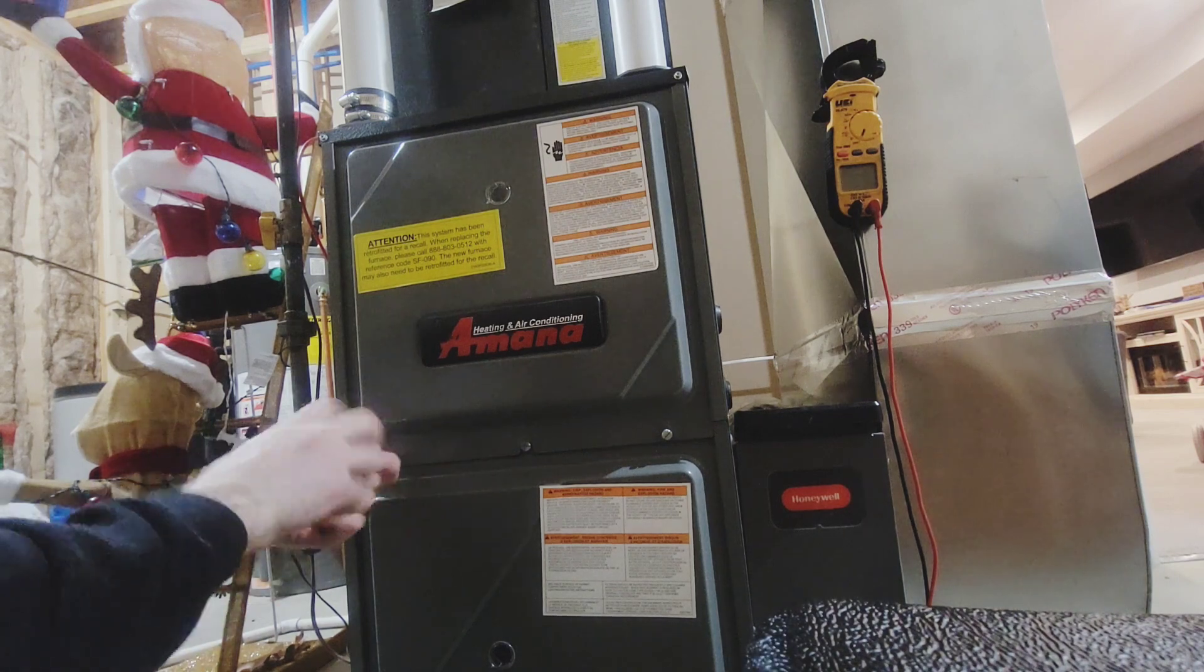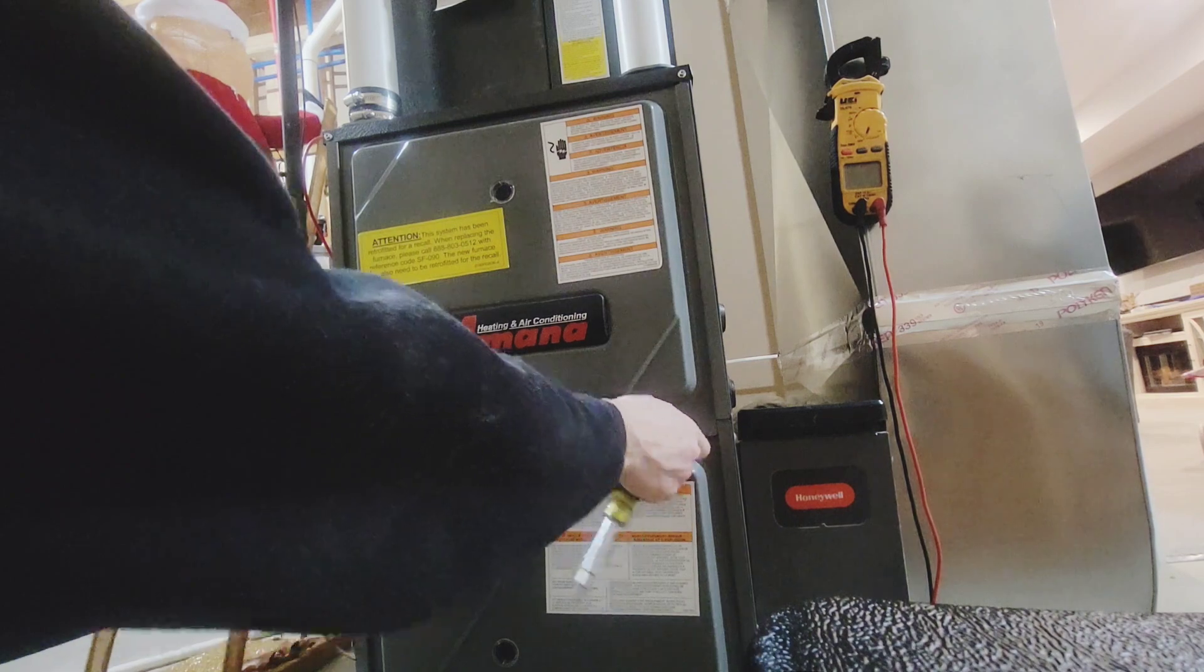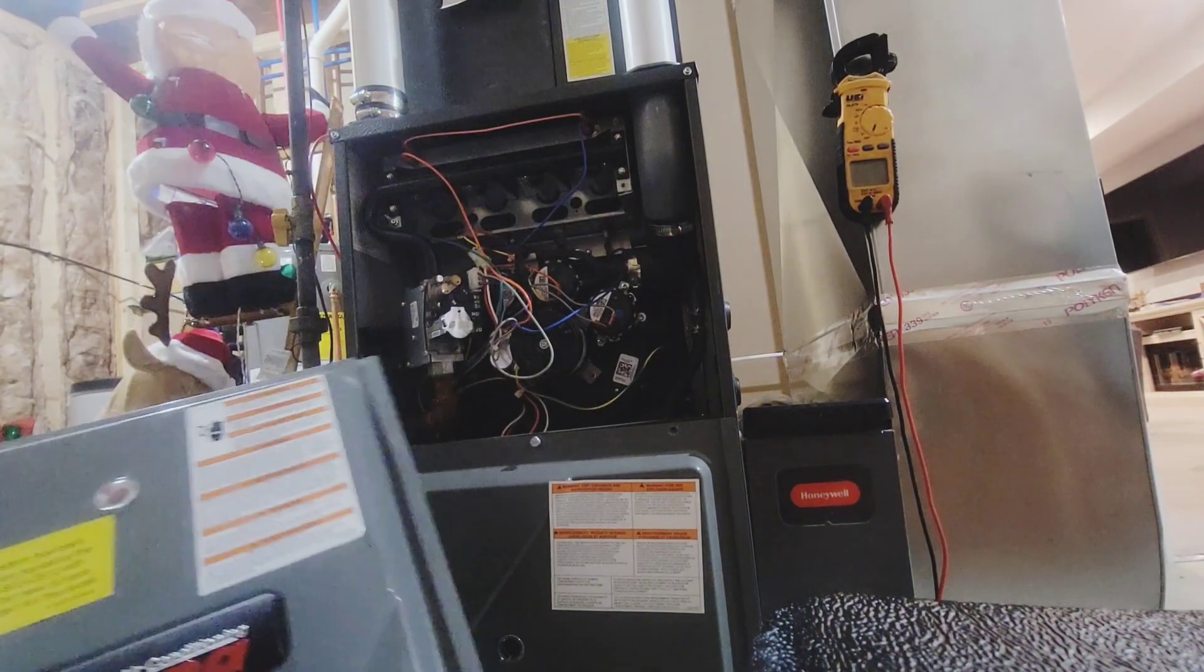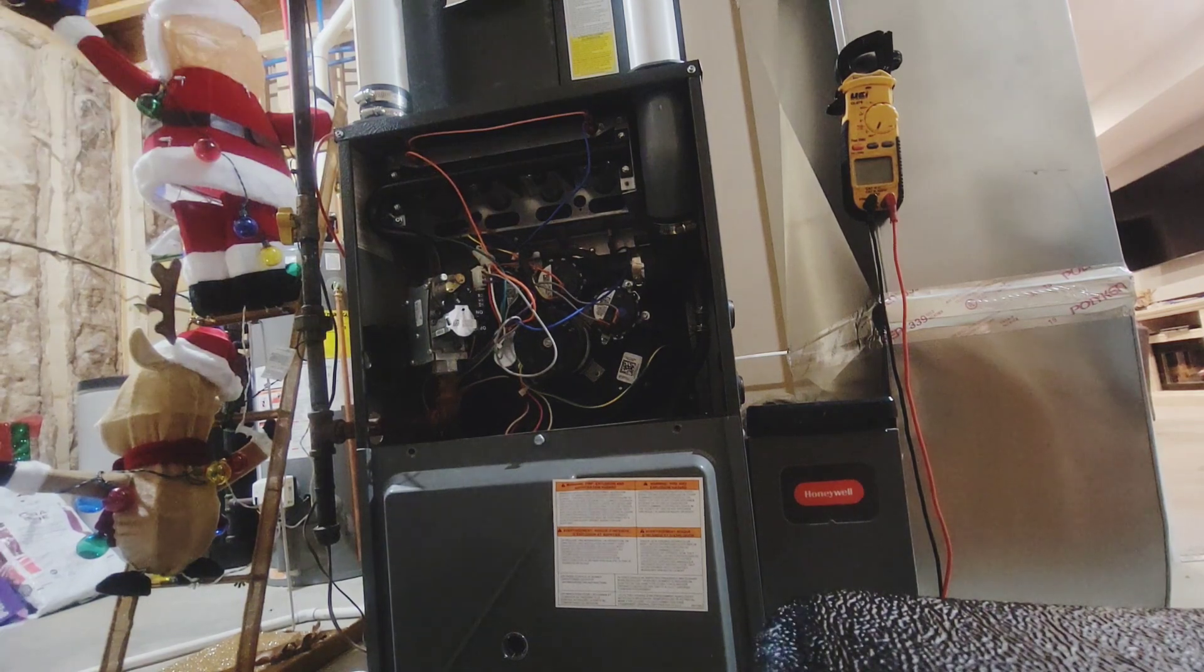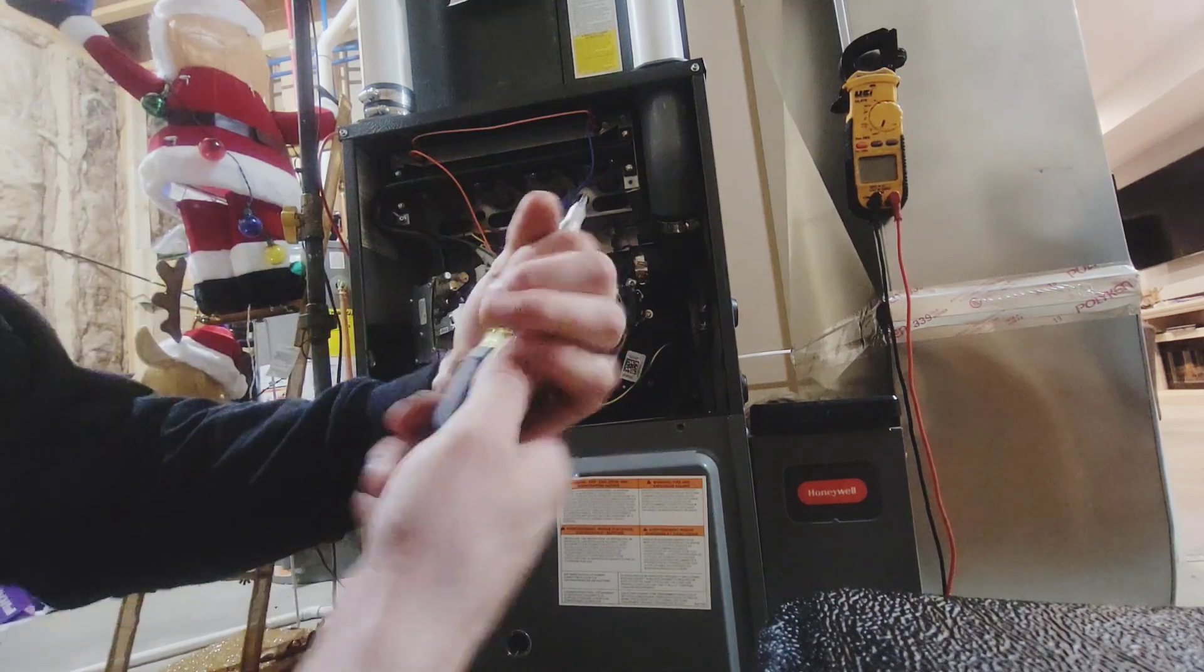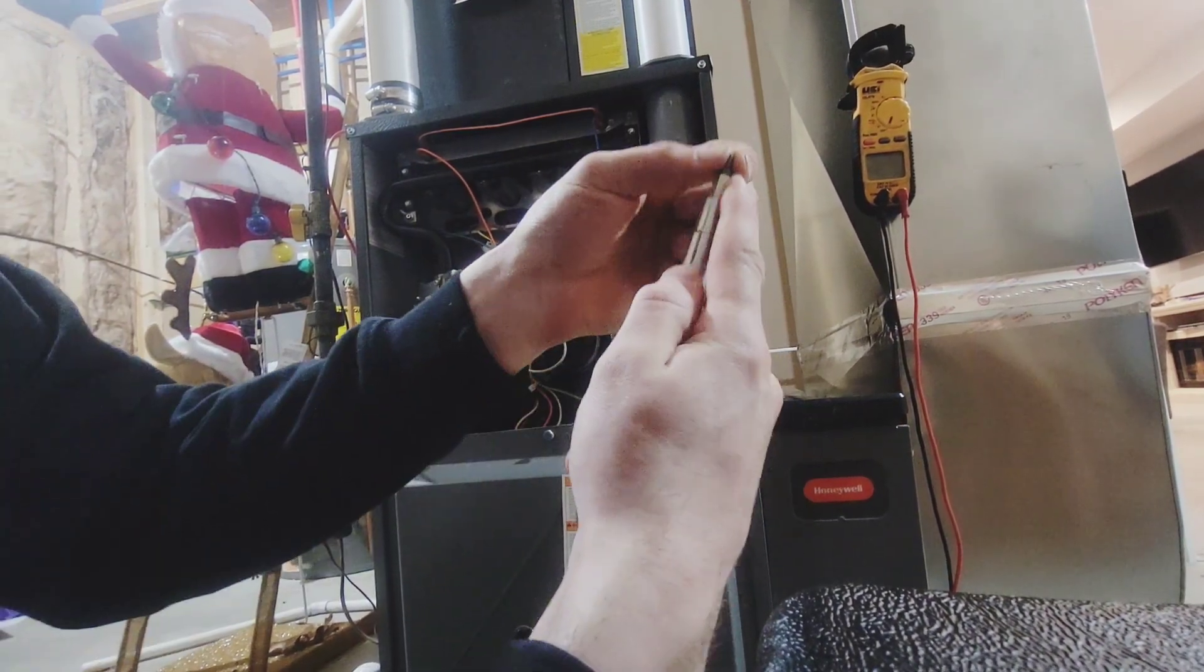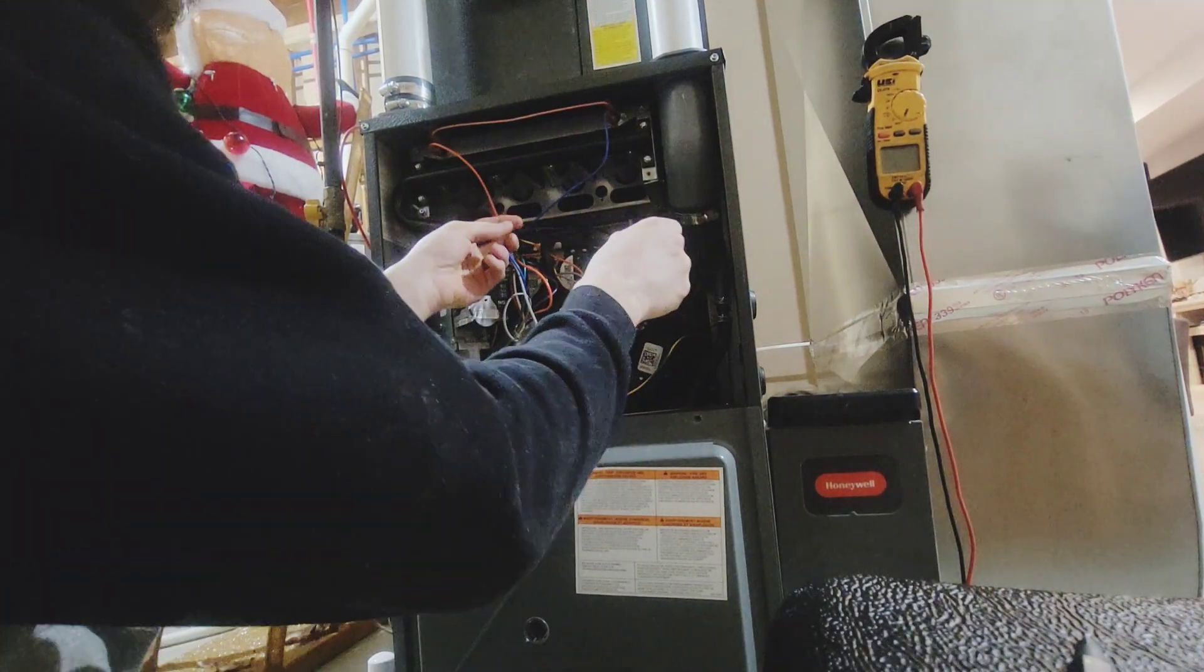Ended up finding that the vacuum switches, pressure switches, were waterlogged. Tried blowing them out, got them up and running for a little bit, but they were definitely slow opening and slow shutting. So we called Amana. They are going to warranty it out. There's about a week left of warranty on this furnace for these customers. We did not install this but we are going to try to save them as much as we can.